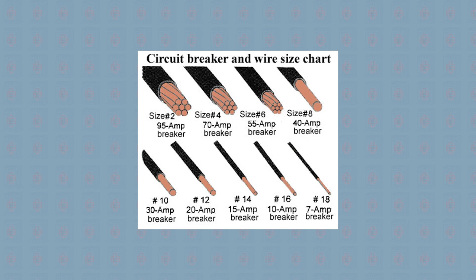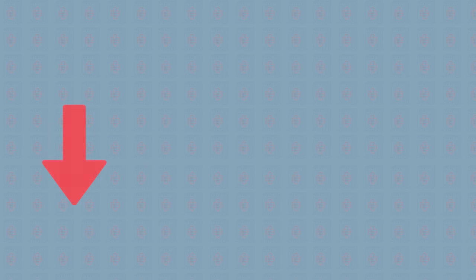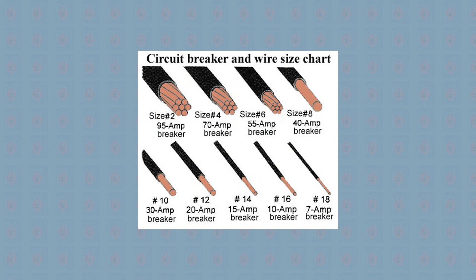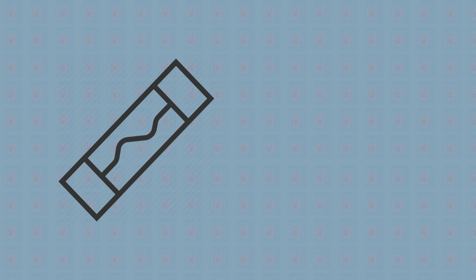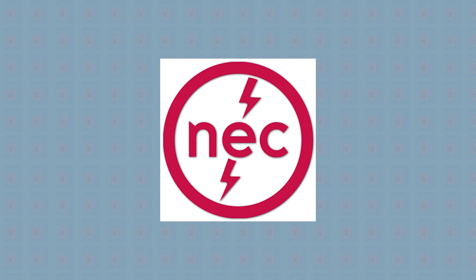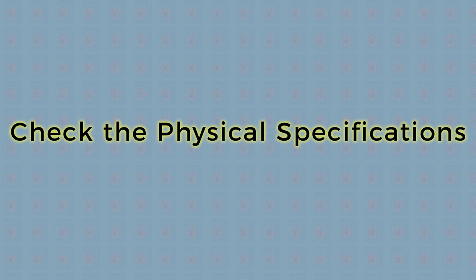You'll find the gauge printed on the wire that will connect to the new breaker. The lower the gauge, the higher the breaker amperage. For example, a 10-gauge wire will need a 30-amp breaker, while a 14-gauge wire requires a 15-amp unit. If adding a new circuit, always account for 125 percent of the circuit's current when choosing an amperage rating. This ensures the safety of the system and is required by the US National Electrical Code.